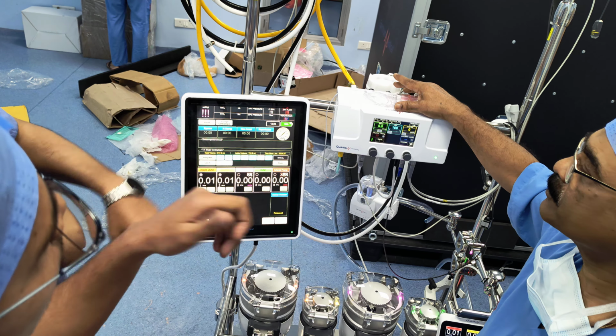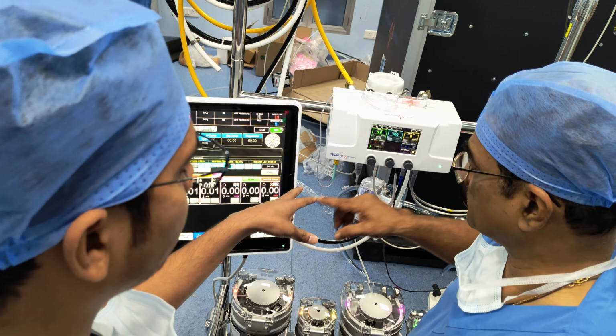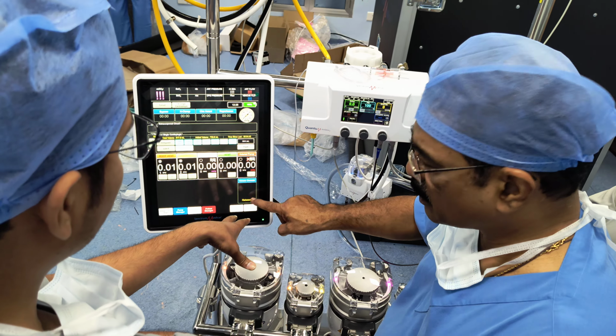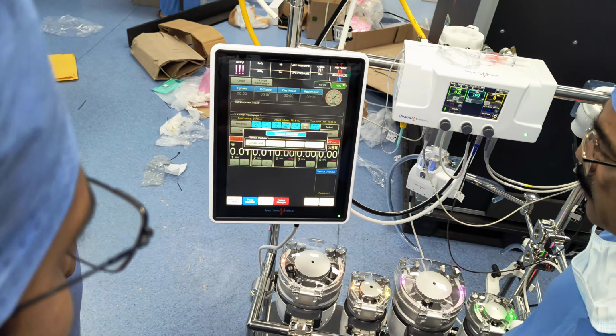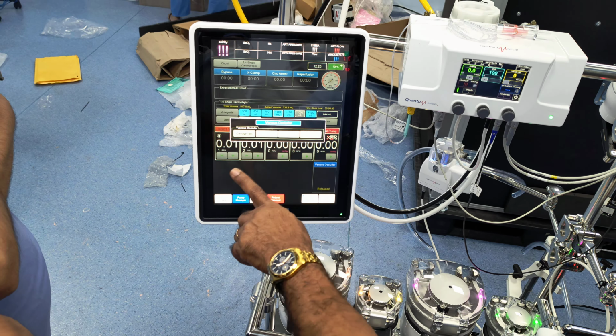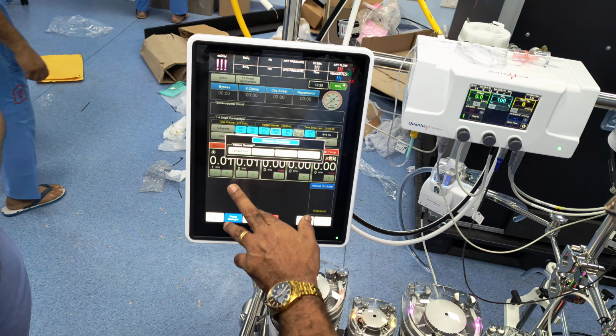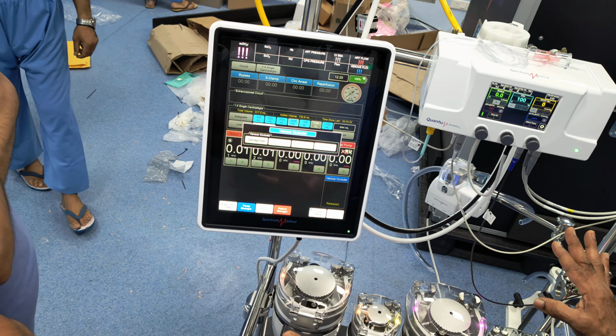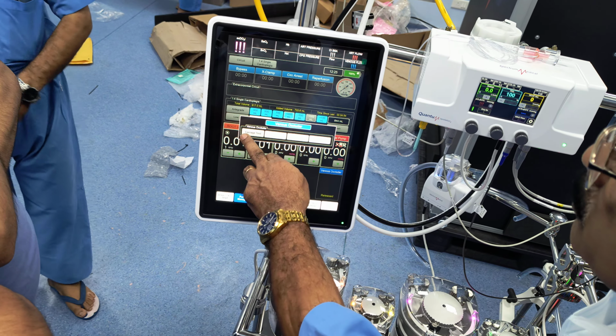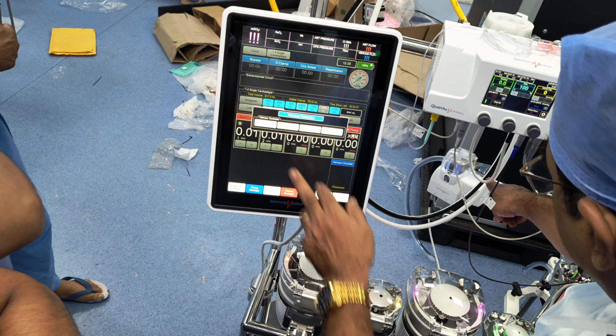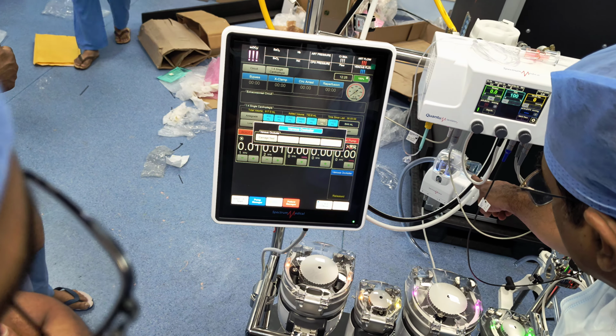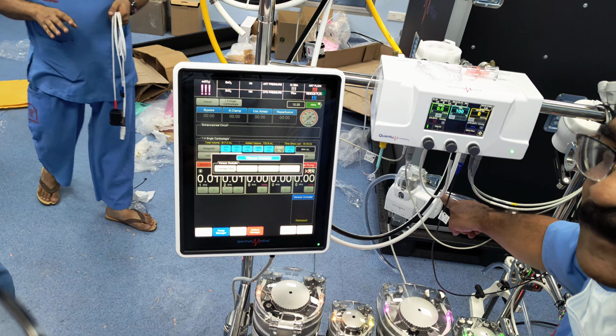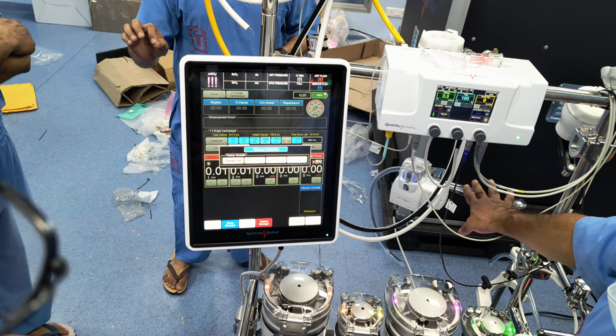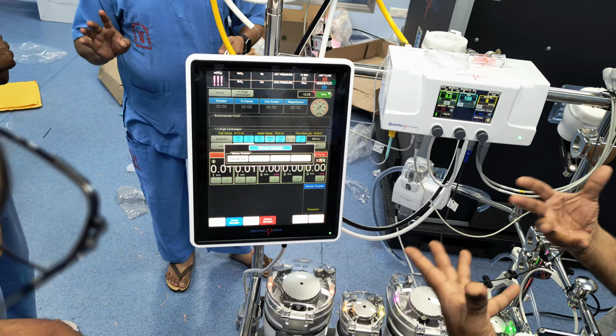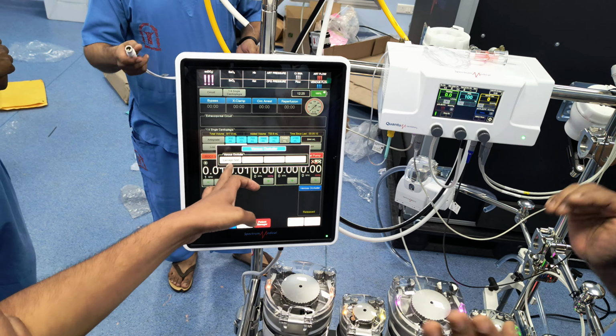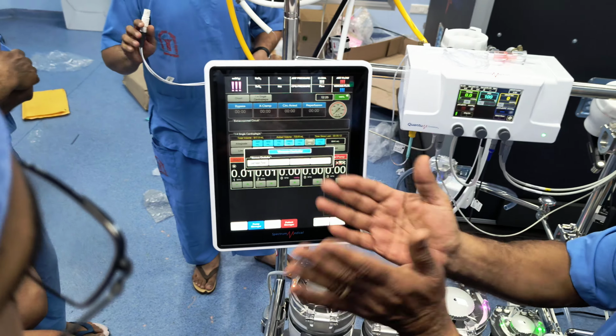This is the, no need to control it. Now this is the venous occluder. So I have clicked it over here. We do a test, we call it a carriage test. So we have just fed the tubing in that. Now we need to check whether it is proper. So when I press on carriage test, see what will happen. Occluder calibration. Okay? No calibration required. It is sensing automatically what tube you have put in. Carriage test means you are testing each one, fine or not. Okay?